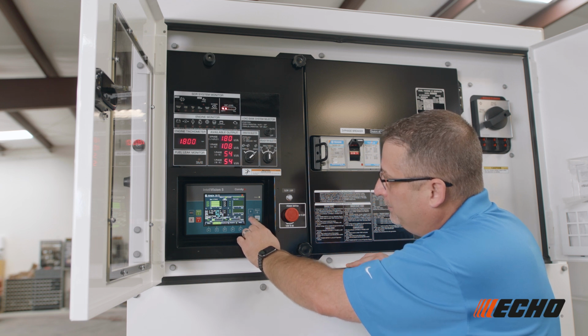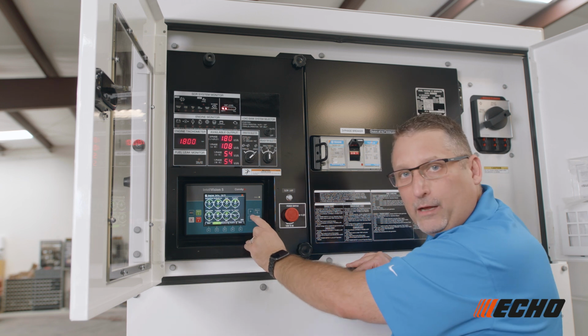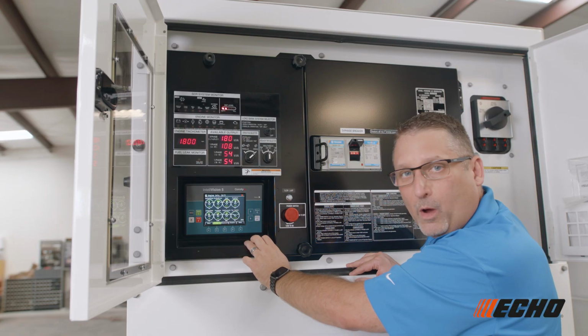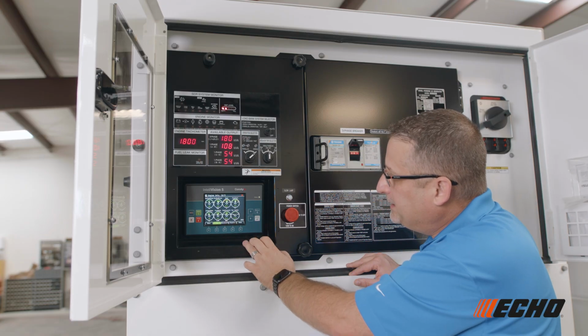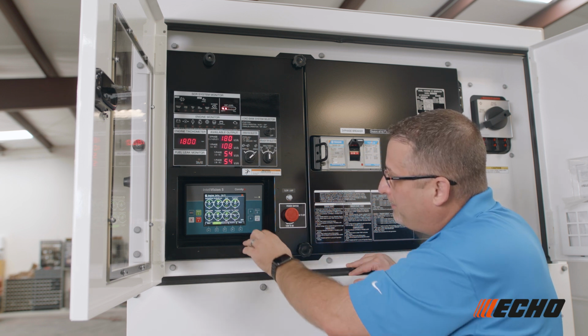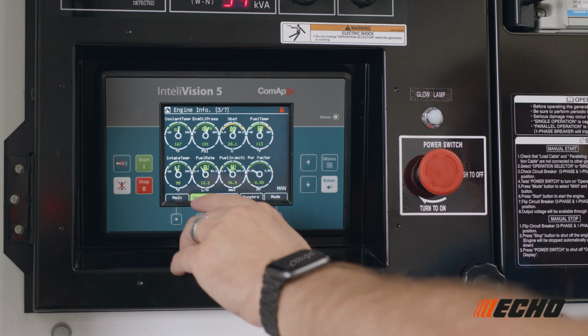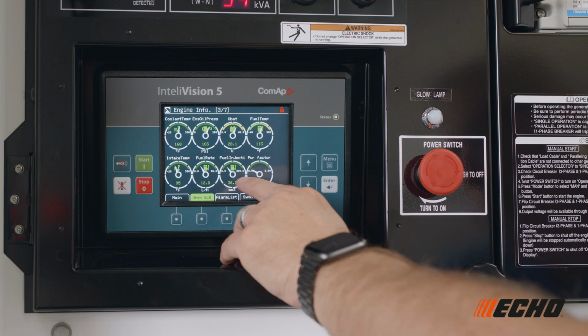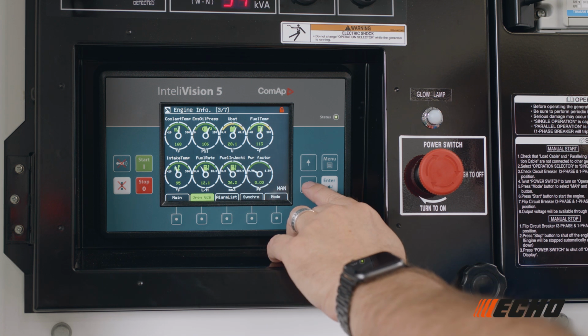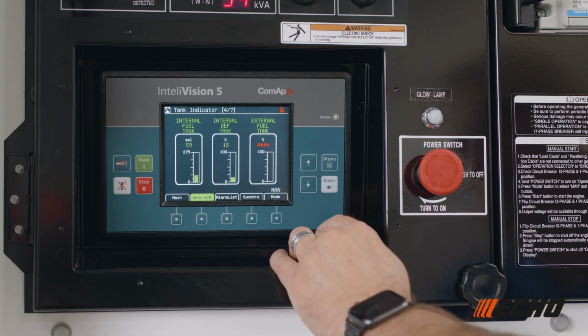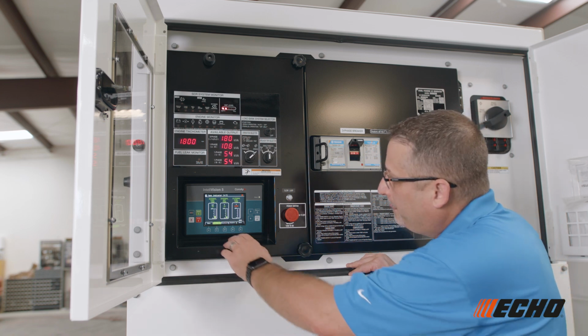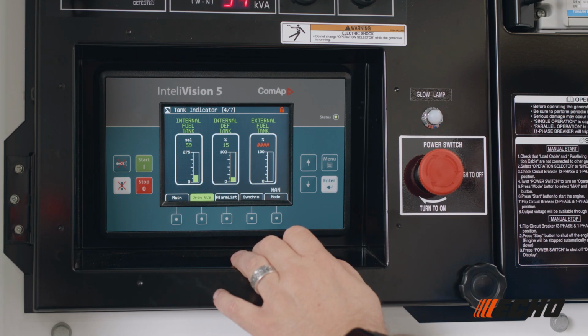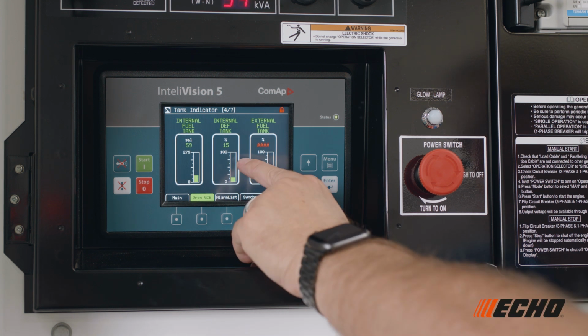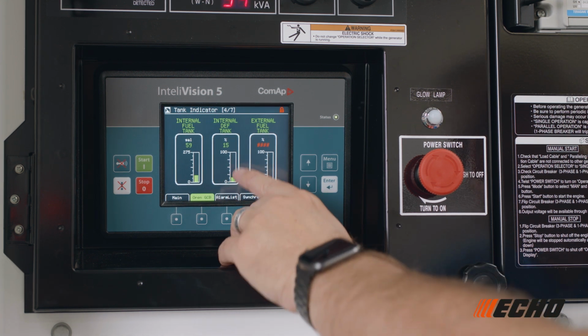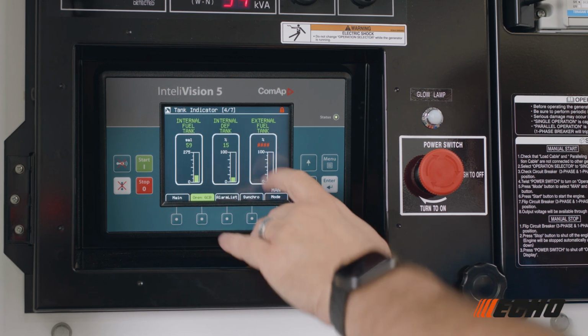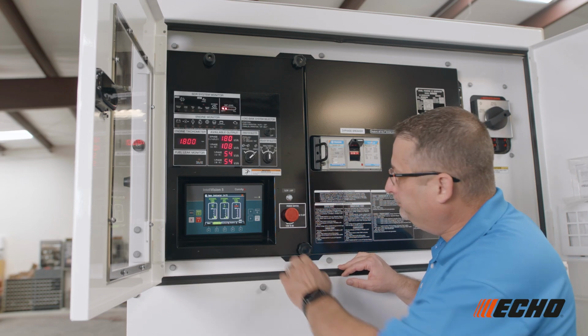As we scroll through all the different metering functions that we have, you have your coolant temperature, which is at 136, 118 on your PSI of your oil pressure. You got your battery voltage, your fuel temperature, your intake, your fuel rate, fuel injectors, and power factor. This gives you an idea of your internal DEF tank as well as your fuel tank. Notice you got 59 gallons on your internal fuel tank of fuel. Your DEF tank is at 15%. This would be your external tank. So if you're on your three-way valves and you have an external tank, we can monitor that tank as well.